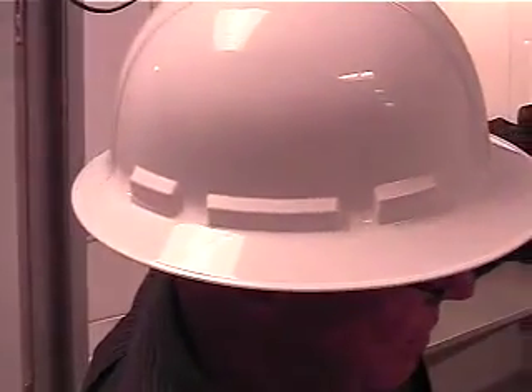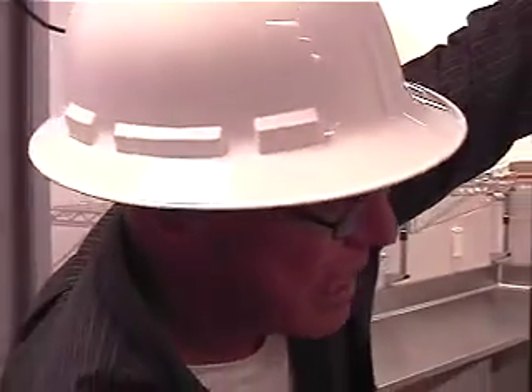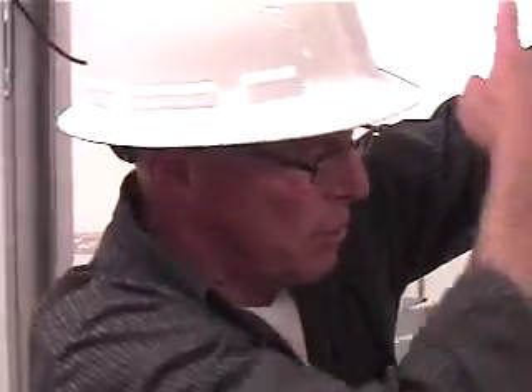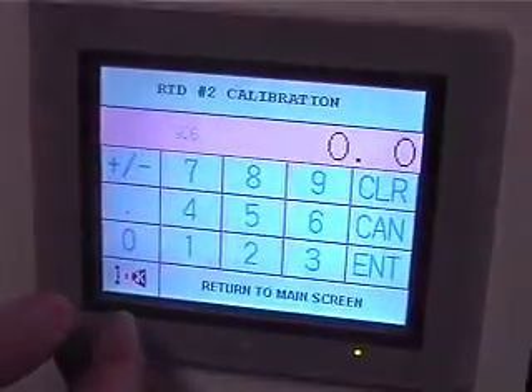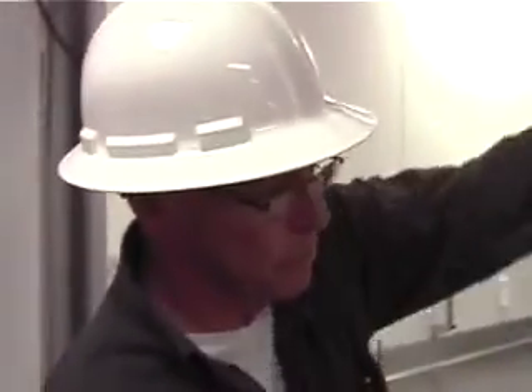That's simple. So we'll check those things, make sure they're close. We generally don't make adjustments if they're within a couple tenths of a degree. The analog input card is 16-bit, and they're very good at what they do these days. You shouldn't have to mess with that too much, but if you have a calibration sequence that you like to do on equipment, you want to put that on your schedule. But that's how tough it is. Just remember that one is up here and two is in here. And two, same thing. Because it's the downstream one, it's the colder temperature. The other one's getting this air coming right in here.